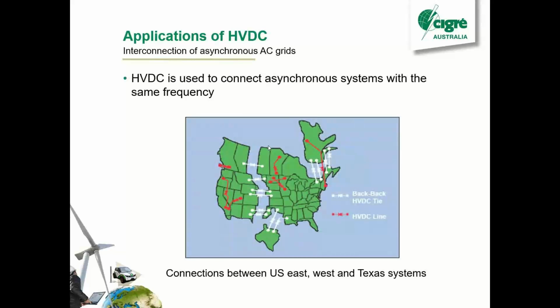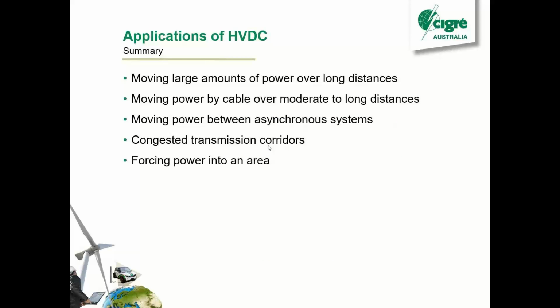You can also use it to connect asynchronous systems, so you can have the same frequency but not be synchronized. Yeah, it doesn't matter with HVDC, it can handle that, no problem. So yeah, in summary, applications: if you want to move a lot of power over a long distance, if you want to move power by cable over even moderate to long distance, and you could even say short distances, to be honest, the charging current is quite a problem on AC, and it gets worse as the voltage goes up. Yeah, if you want to transfer power between asynchronous systems, if you've got congested transmission corridors, or it's hard to get your easements, then HVDC is good.